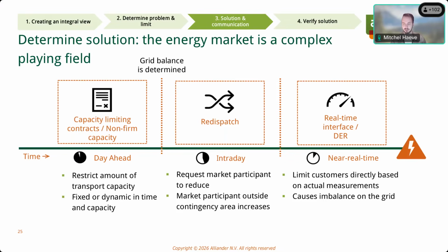At a certain moment in time, at least in the Netherlands, we want to keep the grid in exact balance, so there's as much usage as there is generation, and that is done after the day-ahead domain. That's why when we enter the intraday domain, this is more of a free market format. So the grid is in balance, and we ask a certain customer to maybe help us out. I would ask if somebody could please lower their consumption by 1 megawatt. In order to keep that grid in balance, somebody in the other part of the Netherlands also needs to up or lower that 1 megawatt. Otherwise the grid is not in balance anymore. And these bids all come up at the same time, and an algorithm determines which is the cheapest solution to pick. So that, again, is a more market-based method.